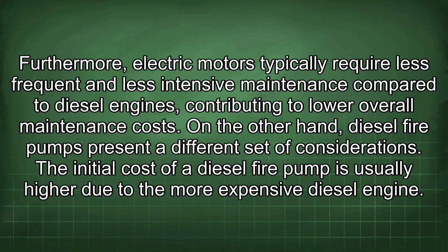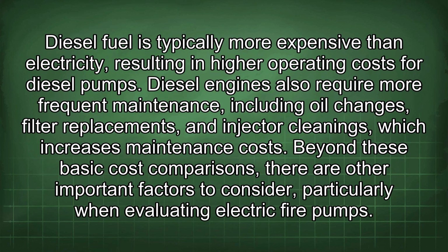The initial cost of a diesel fire pump is usually higher due to the more expensive diesel engine. Diesel fuel is typically more expensive than electricity, resulting in higher operating costs for diesel pumps. Diesel engines also require more frequent maintenance, including oil changes, filter replacements, and injector cleanings, which increases maintenance costs.